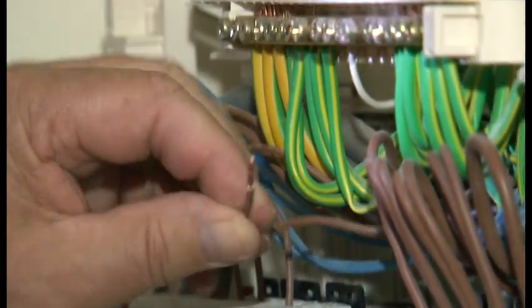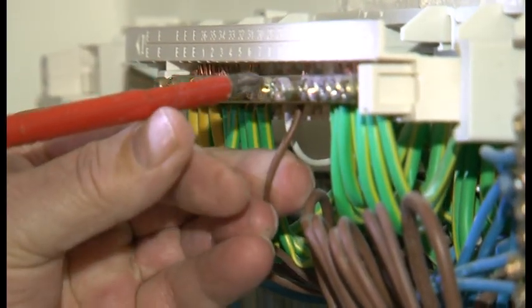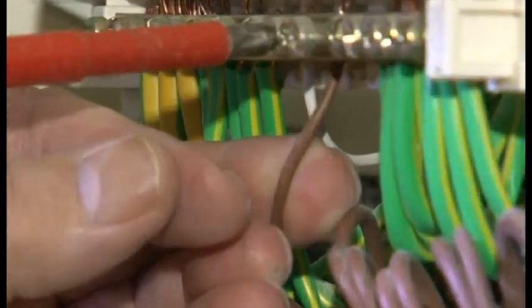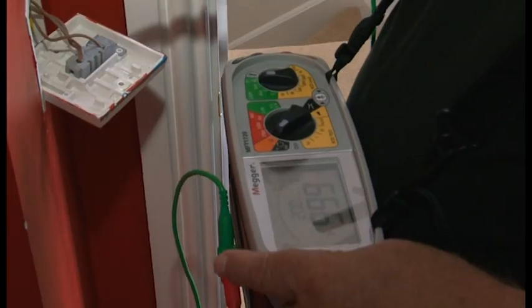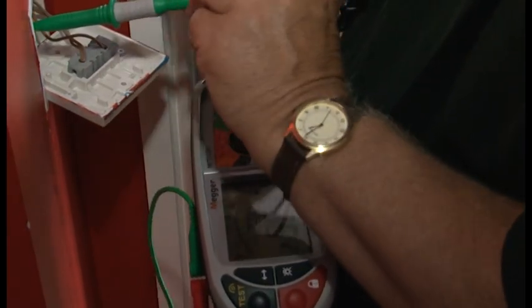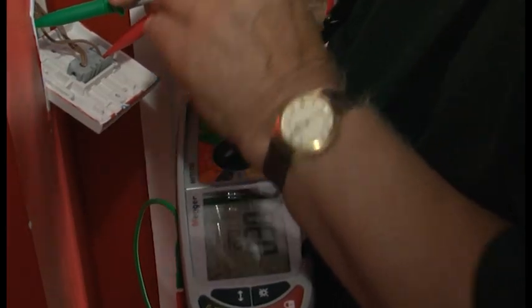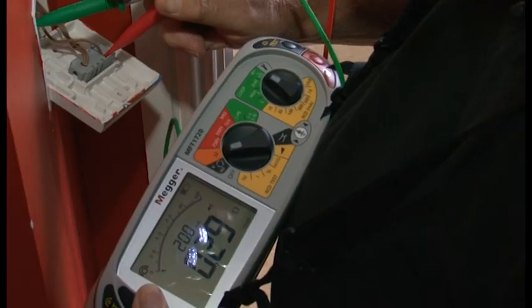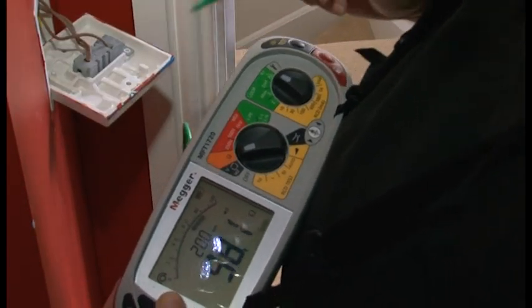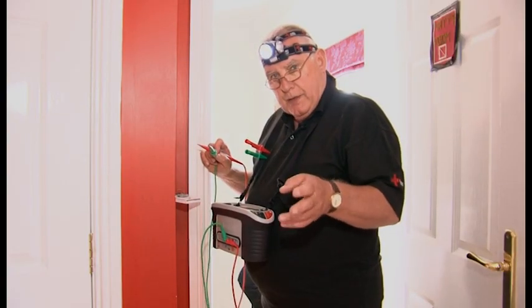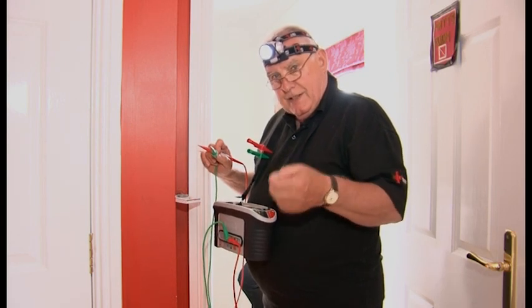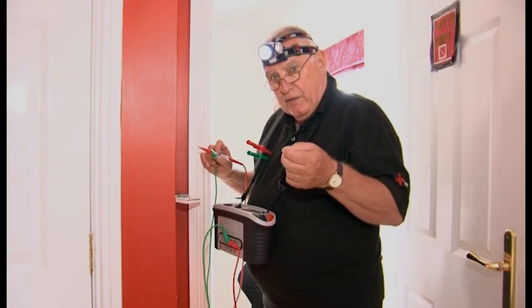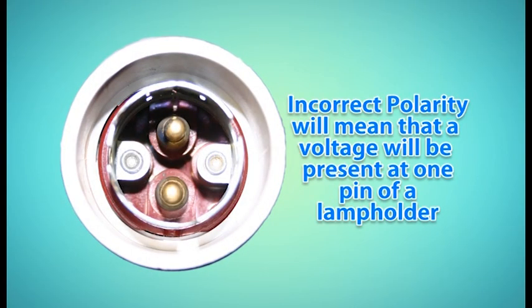At the consumer unit, I cross-connected the line and CPC, as you can see. Right, so I'm going to connect between the CPC and the line. And as you can see, I've got a reading of 0.3 of an ohm. And this I'm going to record as my R1 plus R2. Now, if I've got a high reading here, this more likely would be because I'm coming through the resistance of the lamp, and this would indicate to me that I've got reverse polarity. This means that there will always be a live pin at the light pendant, meaning the users are at risk. It would have to be classified as a code C1 on the report.